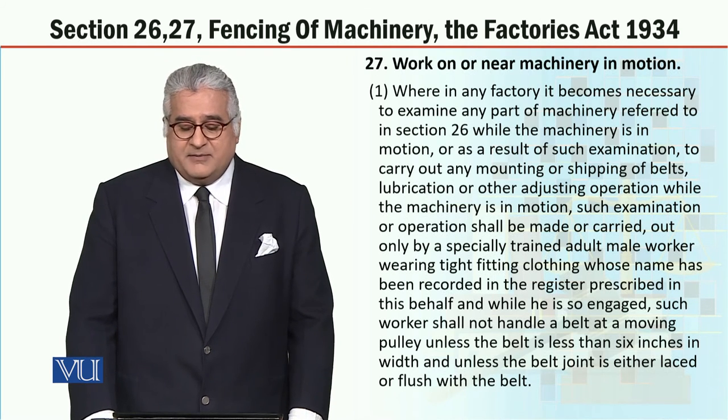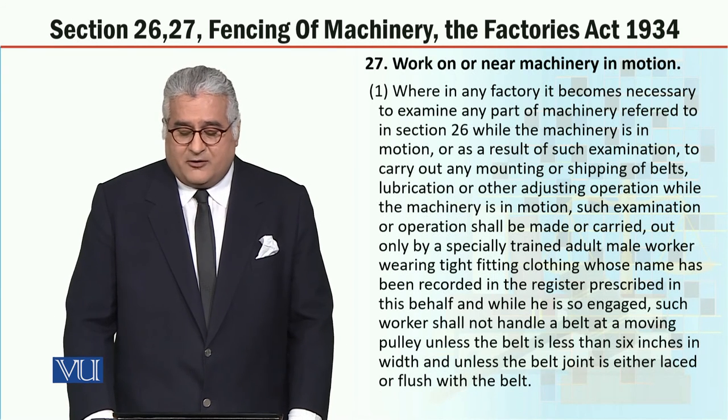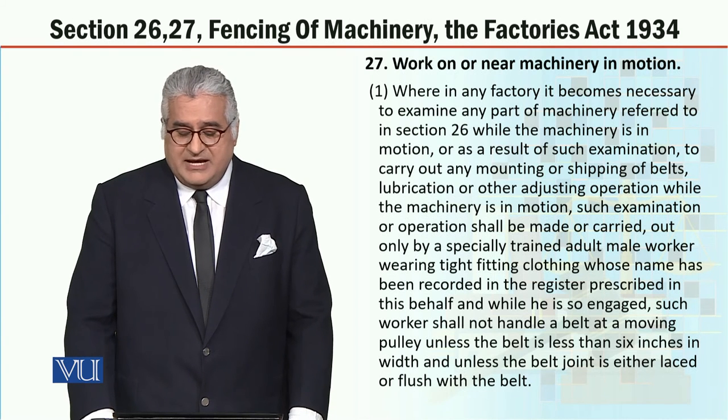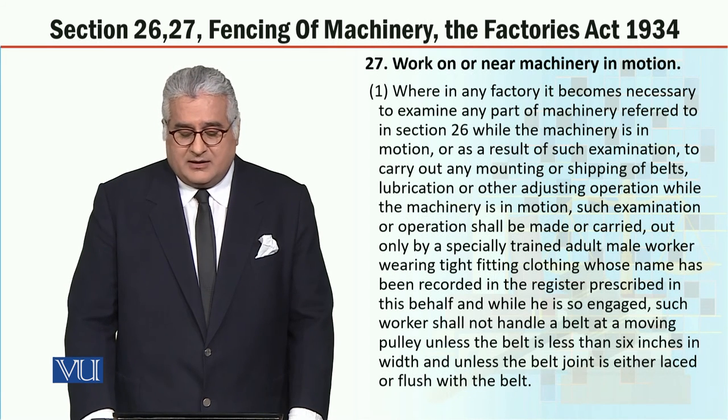Where in any factory it becomes necessary to examine any part of machinery referred to in section 26 while the machinery is in motion, or as a result of such examination to carry out any mounting or shipping of belts, lubrication or other adjusting operation while the machinery is in motion, such examination or operation shall be made or carried out only by a specially trained adult male worker wearing tight-fitting clothing whose name has been recorded in the register prescribed in this behalf. While he is so engaged, such worker shall not handle a belt at a moving pulley unless the belt is less than 6 inches in width and unless the belt joint is either laced or flush with the belt.